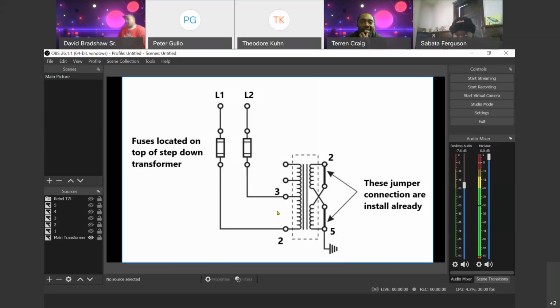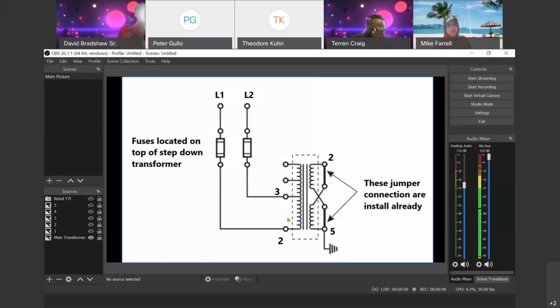I don't know. All we know is we ain't getting 208, we got a problem, don't we? Yeah, that's a fact. Just remember that. If I don't get 208 volts on pin 3, 2 of the transformer, we need to work our way backward, because it doesn't necessarily always have to be the fuse. One of the phases could be out. So if we don't get 208 on pin 2 and 3, we need to work our way back towards the fuse, back to L1 or L2.